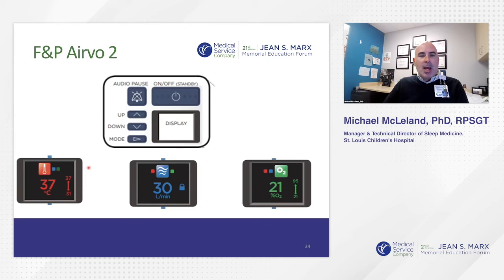You press the mode button again, it'll take you to the liters per minute. Just use the arrows up here to move it up or down to get whatever liters per minute that you want. You press mode again, it'll take you to the FiO2 screen. Again, you can't adjust the FiO2 by the up and down buttons. The only way you can adjust the FiO2 is by bleeding in oxygen from the head wall, if you have one, or an O2 concentrator. The more oxygen that you bleed into the AirVO2, the higher your FiO2 will increase.